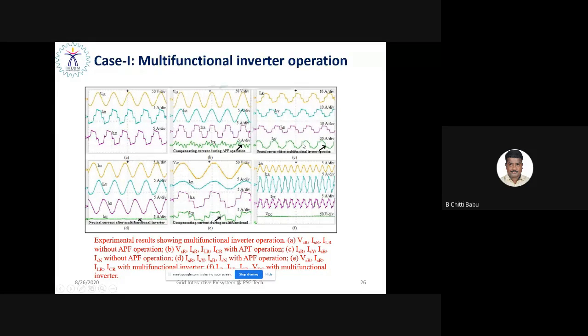But still you can see the neutral current. There is an existence of neutral current because the voltage source inverter, the shunt active power filter, is not used for control. So without the shunt active power filter, there is neutral current, so there must be overheating. Now, as you have connected the three-phase four-leg voltage source inverter, it compensates the harmonic component in each phase, so that the supply currents ISR, ISY, ISB become sinusoidal. Moreover, the neutral current also becomes zero. There is no neutral current. Why? This has been compensated by the fourth leg of the voltage source inverter. So this is the response with the active power filter, with the multifunctional inverter.